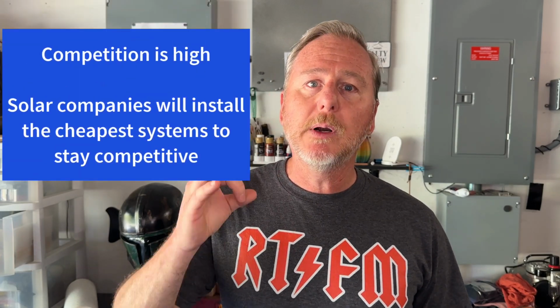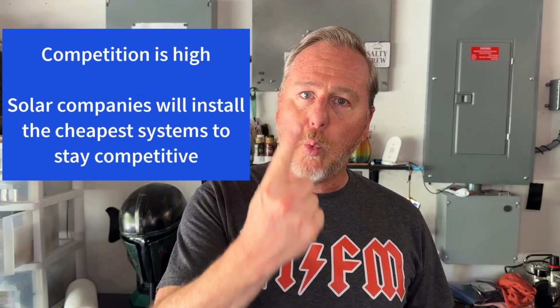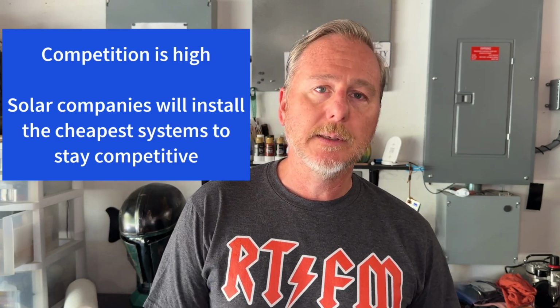If you come to an existing home with solar and you're going to install another battery, it's just not cost effective to rip out that inverter and replace it with a hybrid inverter. Matter of fact, in some places you can't do that. If you have an existing lease or PPA, or you went with one of the big box solar companies, you can't touch that inverter. So you have to leave it there. So then you must go AC coupling. And if you have nothing on your home, you're getting DC coupled because it's the cheaper solution, because you only need one inverter. That's just the way it is. You can challenge me on that and you can pull out an outlier, but the overwhelming majority of the applications are all dependent upon what is installed already.